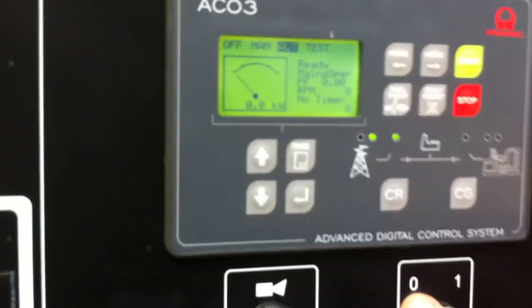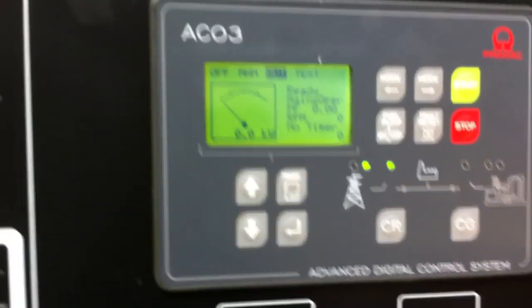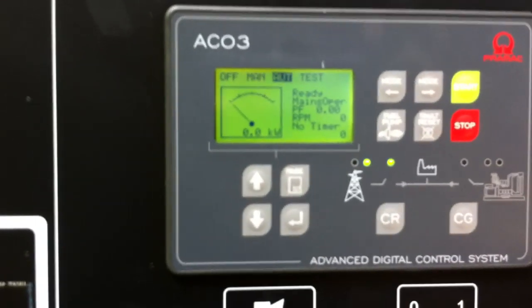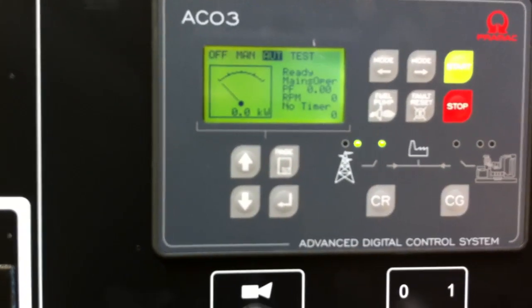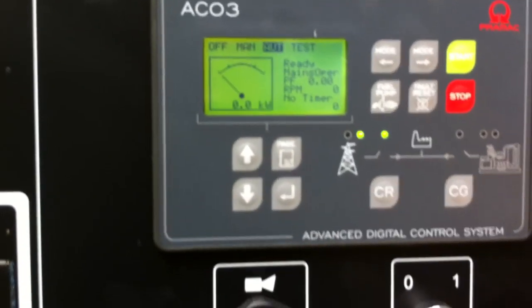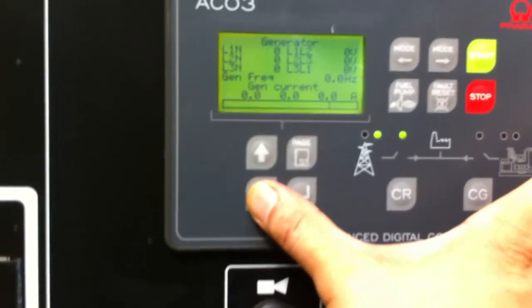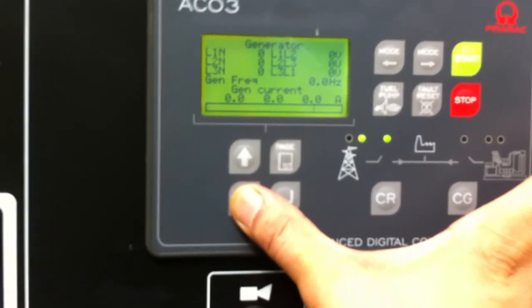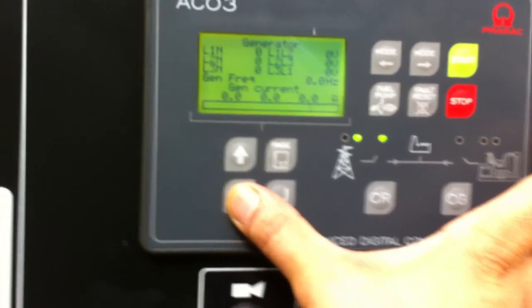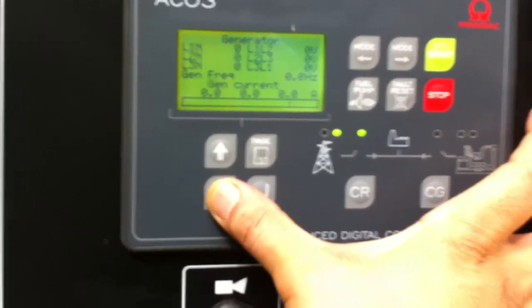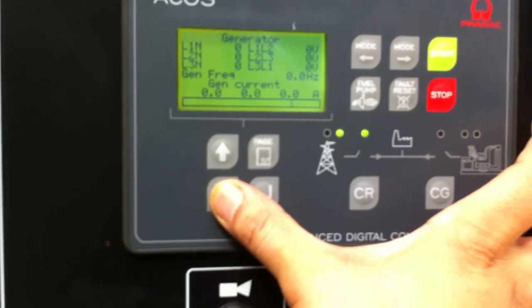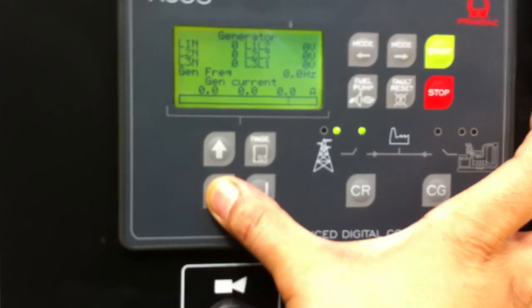On the ACO3 controller, you'll see that it's in ready mode, mains operation, free scroll down. Generator power, there is no power going through the alternator supplying power.